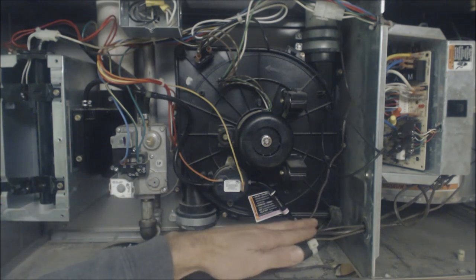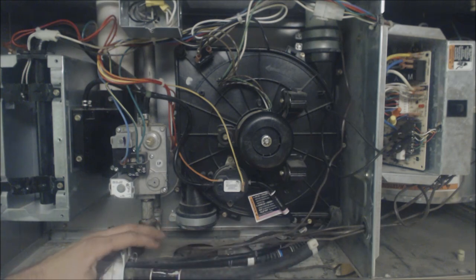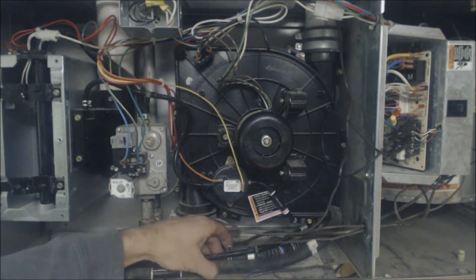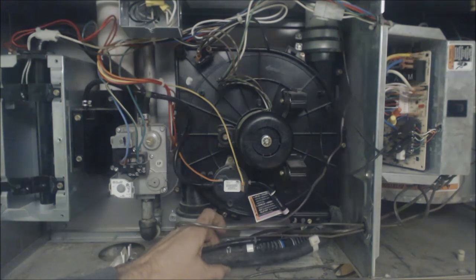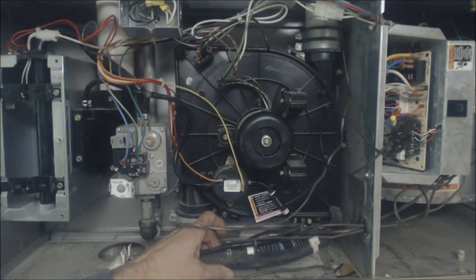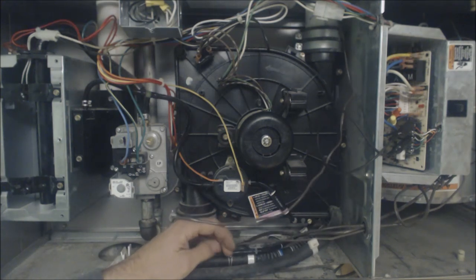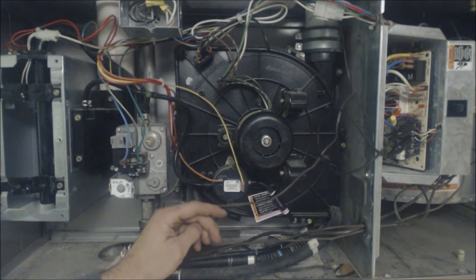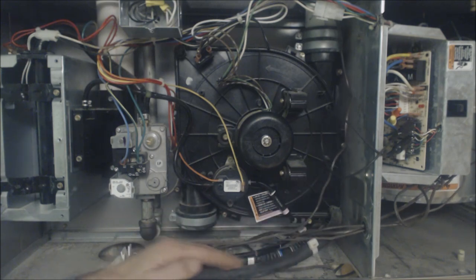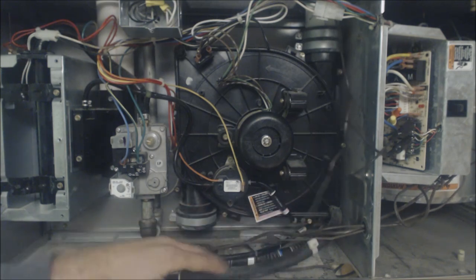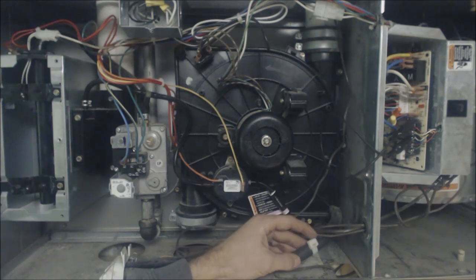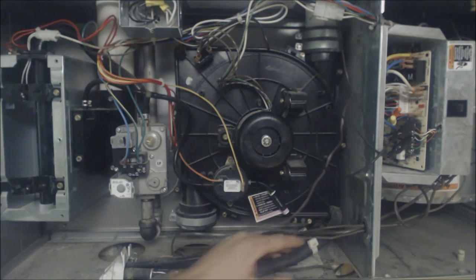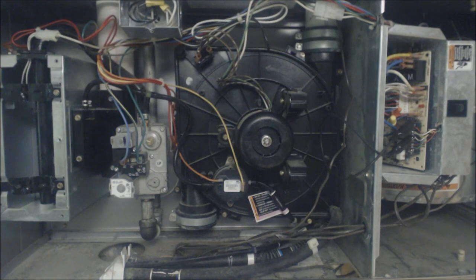Most of the time that is the problem. This should be part of the preventative maintenance schedule right here. If you have a tube that's kinked and it's not allowing the water to drain, you could put a cable tie on it. It applies pressure on all sides, okay, so what it does is it pushes on the pipe on all sides and it basically takes the kink out.